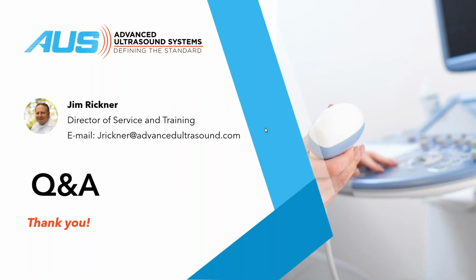That's a tough one. It's a good question. The unfortunate part is many practices, veterinary end users don't use phantoms, so they rely on how they feel about an image, which is a problem to some extent. I wish imaging centers and veterinarians would invest in the phantom so they can do their own evaluations after being briefly trained on phantoms. But really, I think they get to see dropouts. They get to see the lack of detail resolution or even contrast resolution.